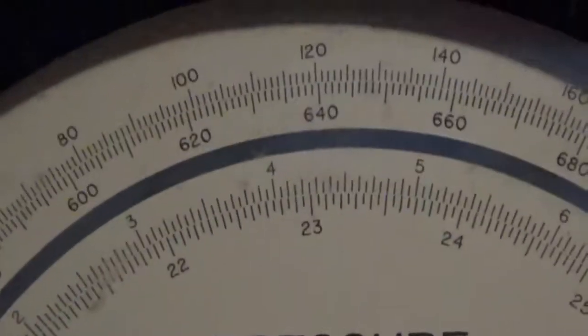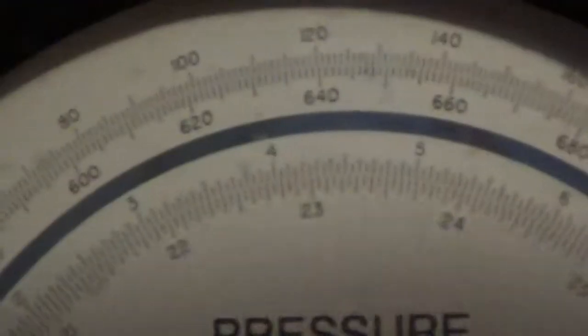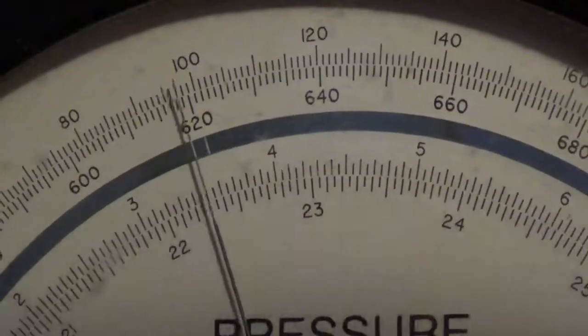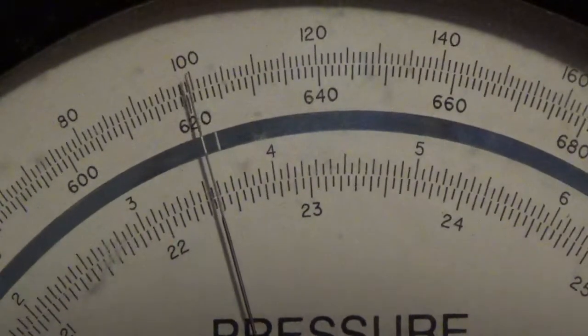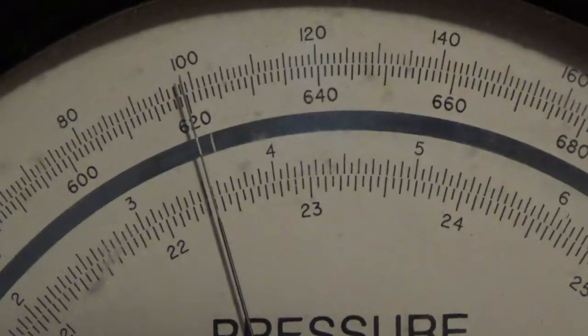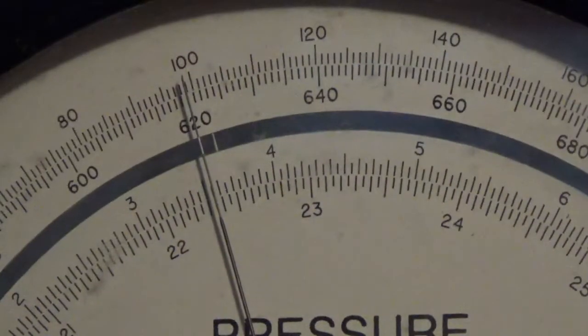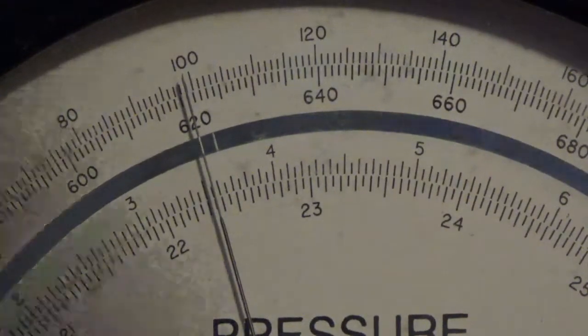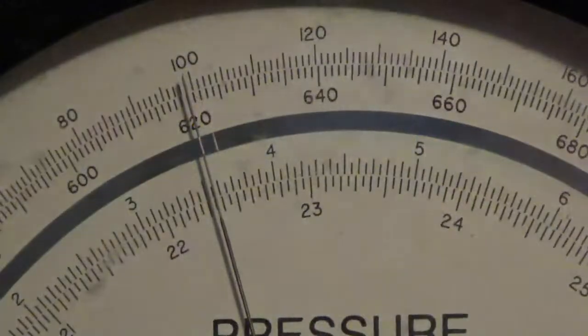Now I'm going to scroll over here to my pressure calibrator, which is now at 0, and I'm going to dial it up to 100 inches of water. Well, there it is, just about at 100 inches. It may not look that way with the camera angle, but it's just about there.